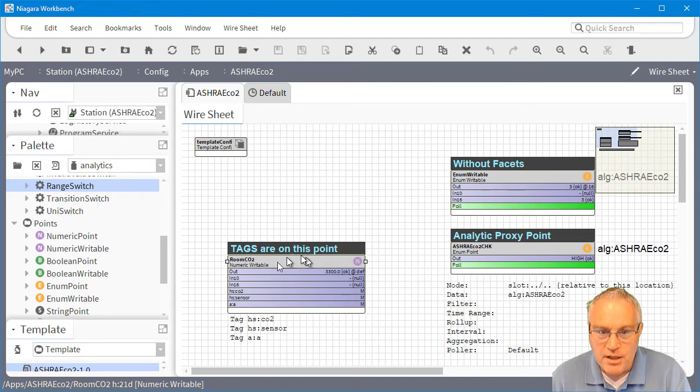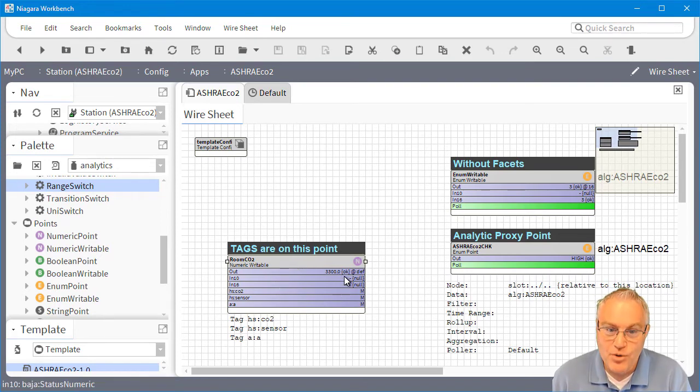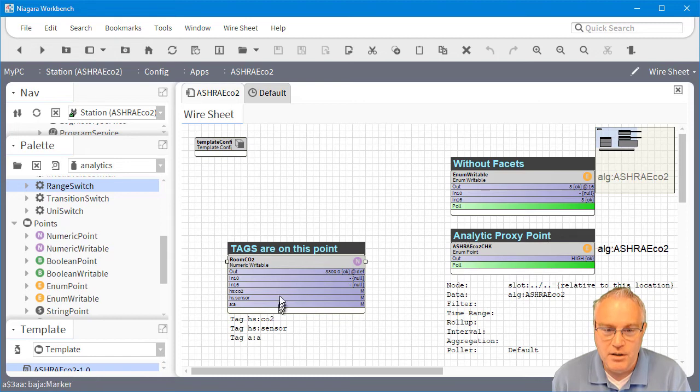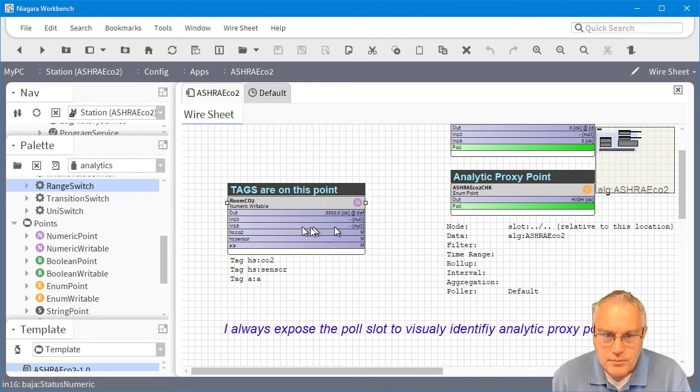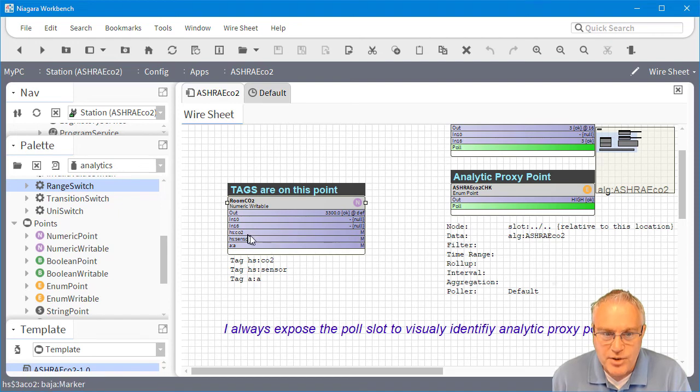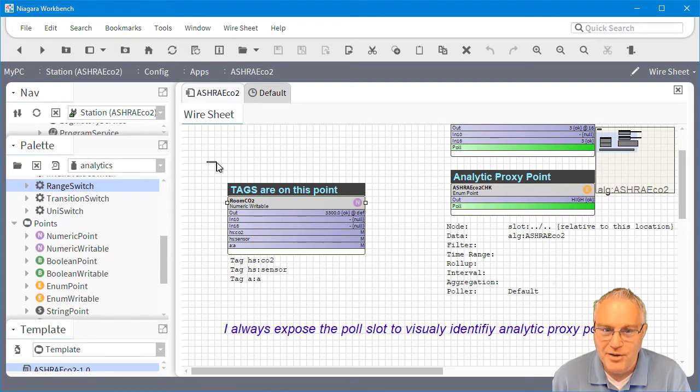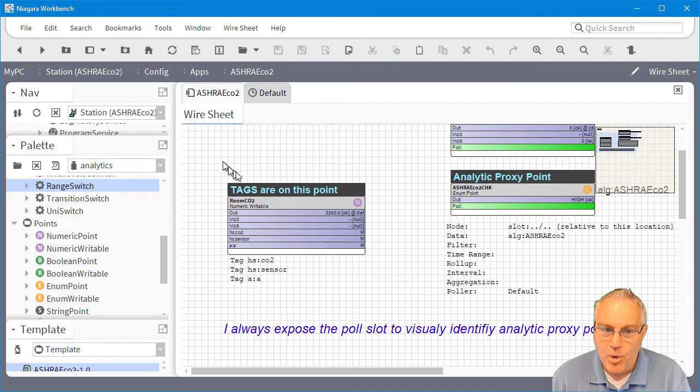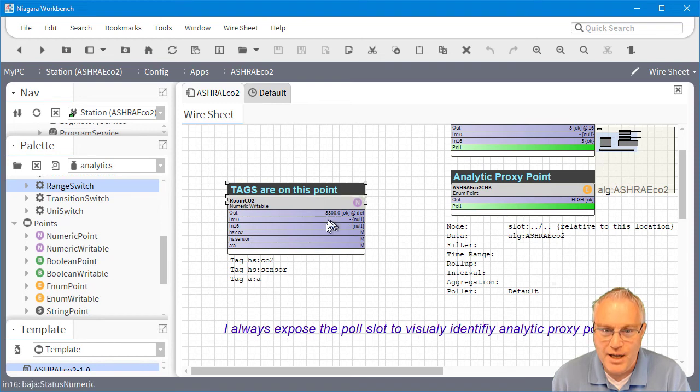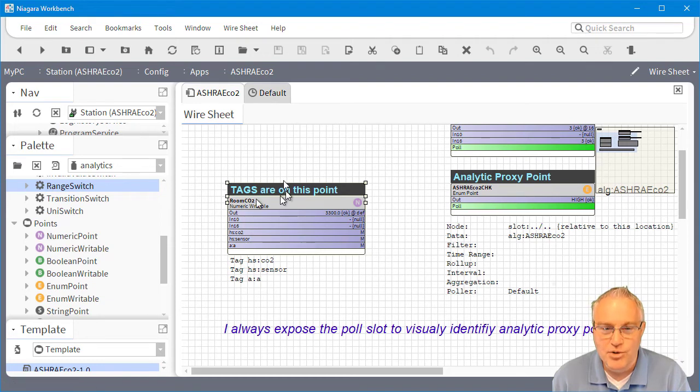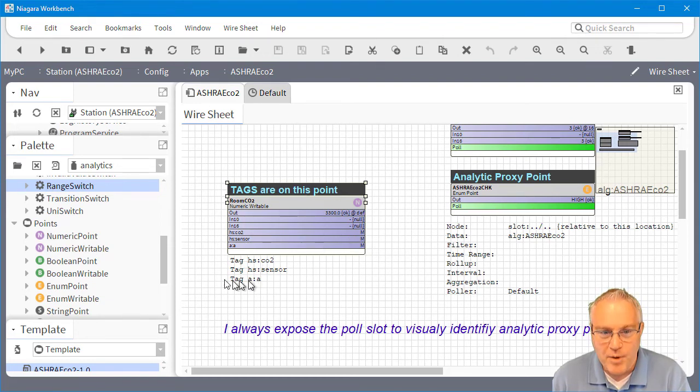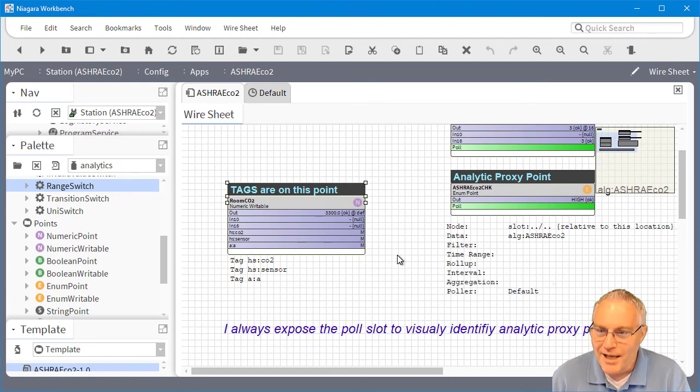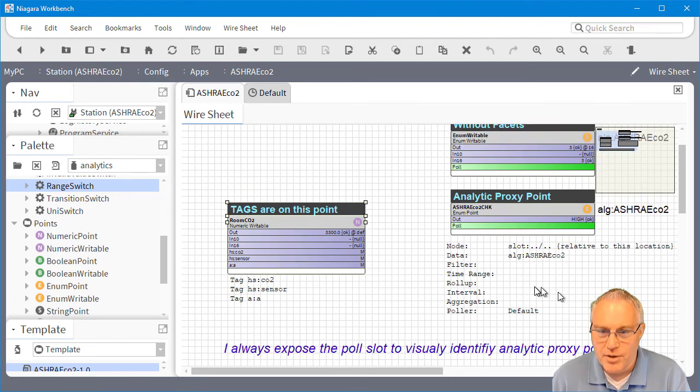This is tagged. This is my actual thing. It has to be in parts per million. I didn't put an actual facet to say parts per million. I'm using parts per million, so my ranges are zero to a thousand. I had to tag it. You'll see CO2 and sensor. I'm breaking my own rule, but you should use tag rules. You shouldn't manually tag your points. I should have a rule that's looking for room CO2. The reason I'm doing this is if you pull this out, I need to make sure you understand that these are the tags that have to be applied to that point. So use a rule, don't do manual tags as I do here. I'm also alerting you that if it doesn't have the a colon a tag, you don't have auto tagging turned on and it won't execute. That's just a little troubleshooting thing.